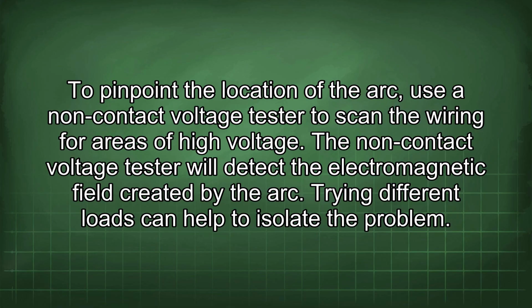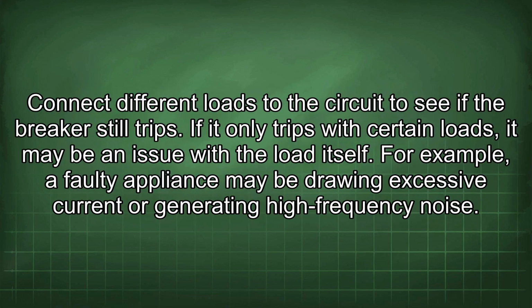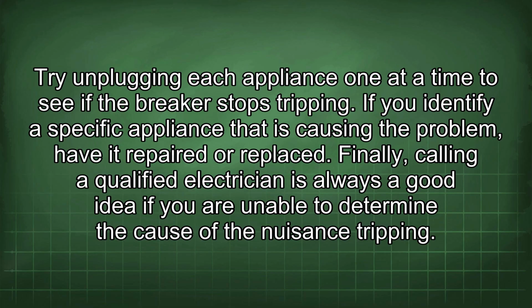Trying different loads can help to isolate the problem. Connect different loads to the circuit to see if the breaker still trips. If it only trips with certain loads, it may be an issue with the load itself. For example, a faulty appliance may be drawing excessive current or generating high-frequency noise. Try unplugging each appliance one at a time to see if the breaker stops tripping. If you identify a specific appliance that is causing the problem, have it repaired or replaced.